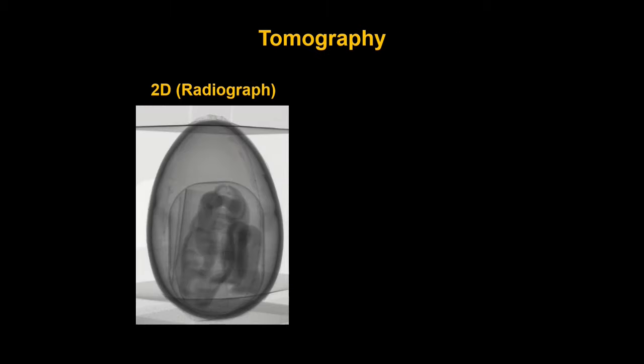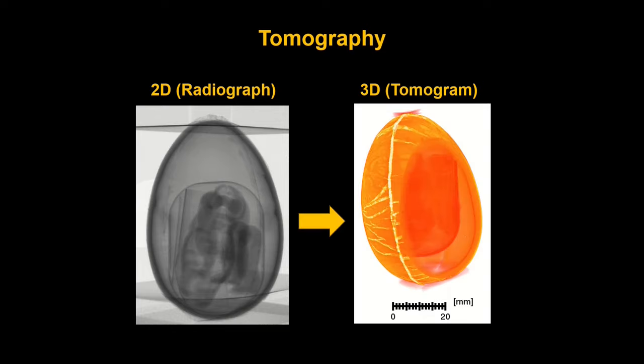So now we know everything about how to get a perfect radiograph. But remember, we want to do tomography, so what we want is a 3D dataset called a tomogram. And in order to get the tomogram, we're going to have to take advantage of the fact that the sample is on a rotating stage. We don't have to gather just one radiograph. We have to gather a collection of radiographs that we call projections. And we have to take these projections at various angles around the sample so that we can see the full volume of the sample as we rotate it. And we have to gather thousands of these projections in order to get a very high quality tomography. And the question remains, how many projections do we need?